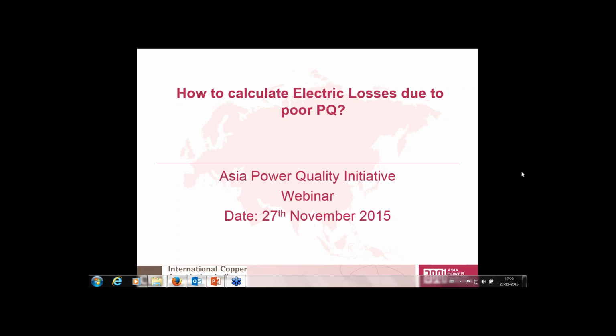As far as my knowledge is concerned, there is not much standard regulation of power quality in India, but there are some individual regulations. Typically, like maybe for lighting systems, they have put some standard. They have put some typical standard for voltage fluctuations. Like typically in urban areas, earlier they used to say plus minus 6%, and for rural areas they say plus 6% and minus 15%. Because in rural areas it is very difficult to maintain the voltage level of the order of plus minus 6%. So that is about voltage.